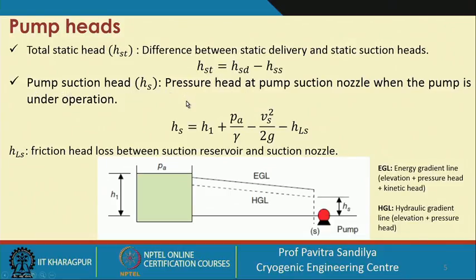Next we have the pump suction head. Here we are finding the pressure head at the pump suction nozzle when the pump is under operation. The difference from the static case is that when the pump is operating there is a kinetic head and also pressure loss due to friction. So the pump suction head under operation includes both the kinetic head and the frictional loss inside the pipelines, and HLS is the friction head loss between the suction reservoir and the suction nozzle.